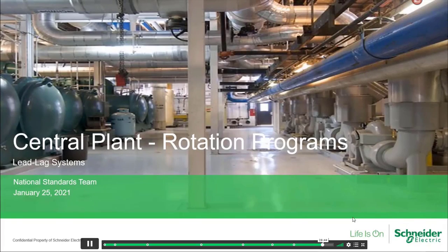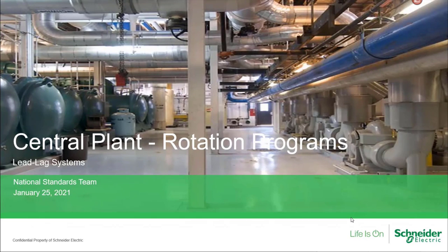All right. Well, thank you, Justin. That was awesome. I hope everybody sees an immediate need for a program like this. What really stands out to me is it's less about lead lag or the order of equipment, and more about intelligently deciding which piece of equipment should stage up next and which piece of equipment should stage down next. Obviously, if something is in hand, it's not a good candidate to stage down. If something has failed, it's not a good candidate to stage up. And this is going to automatically keep everything in the right position so that you see less downtime and less maintenance requirements through rotation. So I hope you all see a use for this soon in a project coming up.